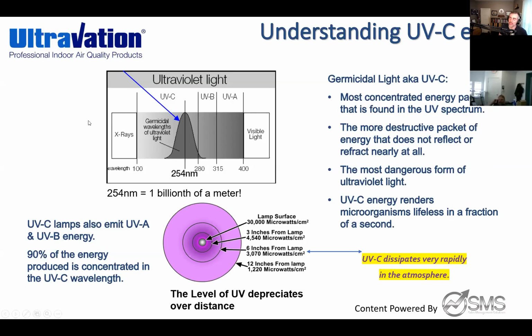So you need to make sure every technology piece you're installing in an HVAC system is using a UVC wavelength bulb. Yes, UVA and UVB are also coming off of a lamp like this, but the most important thing is it has to be UVC class, because it's the most destructive component of UV light. At 254 nanometers, if you want that buzzword, this is the most dangerous form.